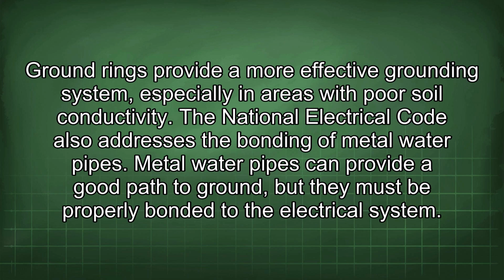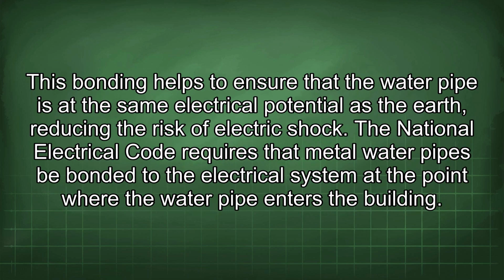The National Electrical Code also addresses the bonding of metal water pipes. Metal water pipes can provide a good path to ground, but they must be properly bonded to the electrical system. This bonding helps to ensure that the water pipe is at the same electrical potential as the earth, reducing the risk of electric shock. The National Electrical Code requires that metal water pipes be bonded to the electrical system at the point where the water pipe enters the building.